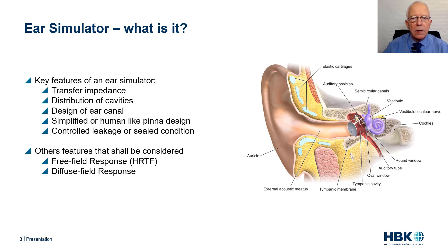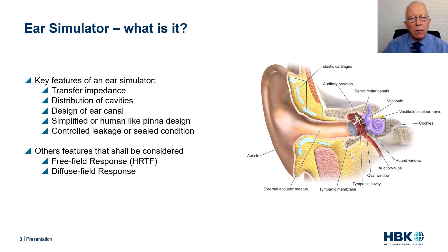The purpose of an ear simulator is to replicate specific properties of the human ear. Important features of an ear simulator are the acoustic impedance, distribution of cavities for realizing a specific acoustic impedance, design of the ear canal, pinna design — simplified or human-like pinna — controlled leakage, or sealed conditions. Other features shall be considered when embedding the ear simulator in a head and torso simulator, or HATS for short, and that is the free field response or HRTF — head related transfer functions — as well as diffuse field response.